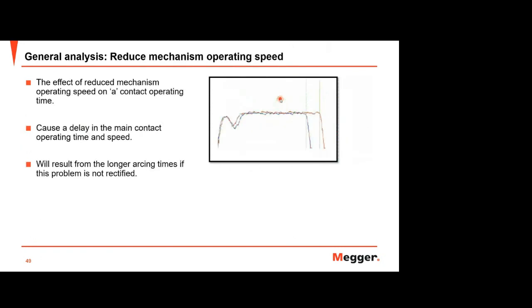And this one reduces mechanism operating speed. If you see from here to here it is similar, but only the end of the current going down is different. So this mostly affects the speed, the contact operating time. This is affected by maybe some mechanical issue on your circuit breaker. Yeah, this will give you delay in main contact operating time, but more importantly is reduction in speed at which the contact is moving, that part, this one.